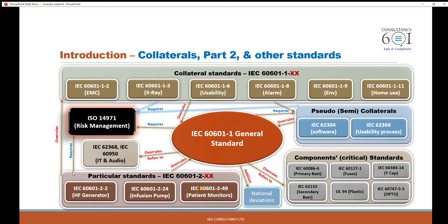If you have the same requirement in the particular standard and the general standard, you will need to satisfy the particular standard when there is a conflict with the general standard. So the particular standard takes priority over collateral and also over the general standard. The pseudo-collaterals also take priority over the general standard.